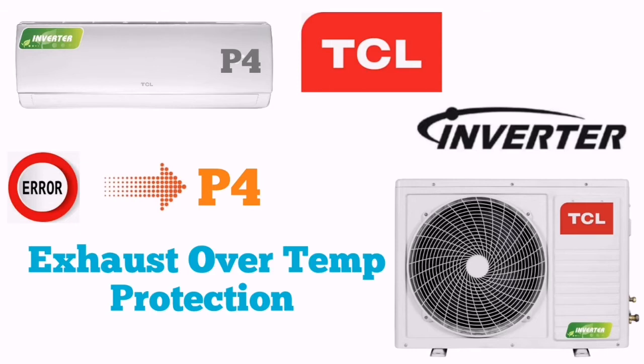And if it is clear, and again if it is showing the same error, then you have to check the refrigerant. If the refrigerant is in shortage or something like that, if there is any leakage you find in your piping or something, then you have to recharge the refrigerant and your unit will be working.